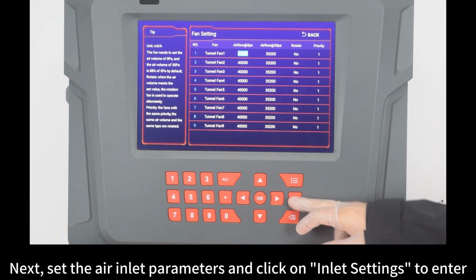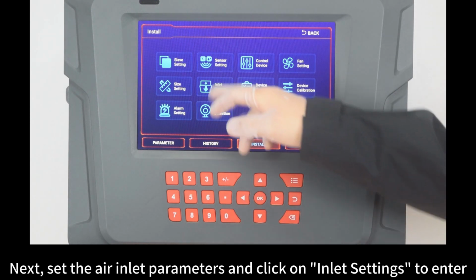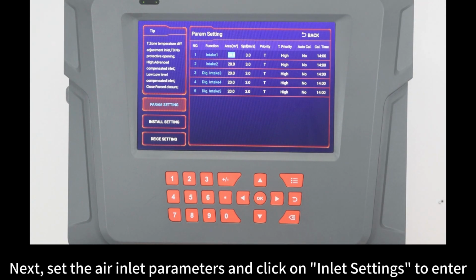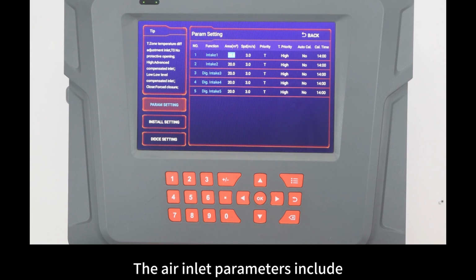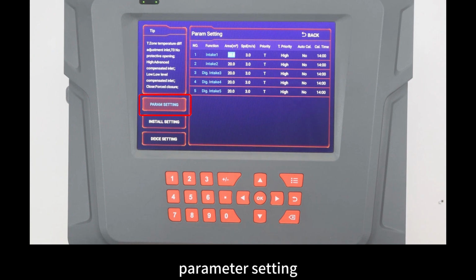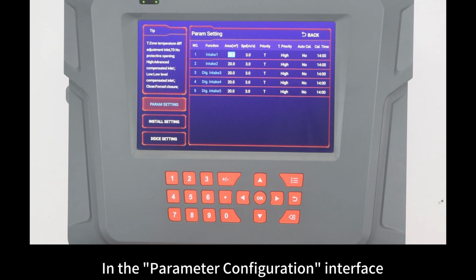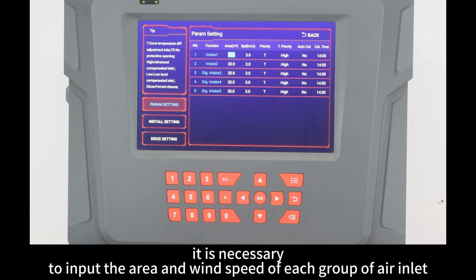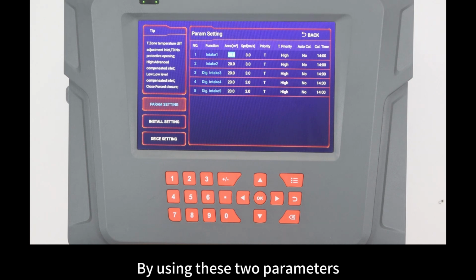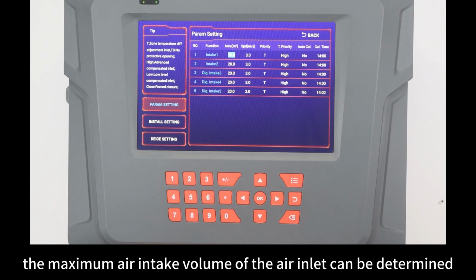Next, set the air inlet parameters and click on Inlet Settings to enter. The air inlet parameters include Parameter Setting, Installation Setting, and Device Setting. In the Parameter Configuration interface, it is necessary to input the area and wind speed of each group of air inlet. By using these two parameters, the maximum air intake volume of the air inlet can be determined.